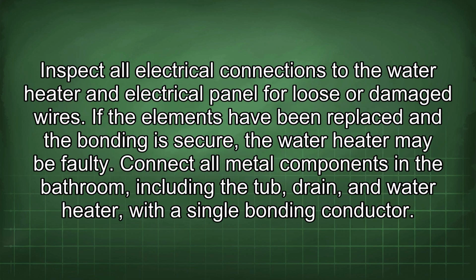Temporarily disconnect the bonding wire between the water heater and tub drain to eliminate the possibility of a ground loop. Inspect all electrical connections to the water heater and electrical panel for loose or damaged wires. If the elements have been replaced and the bonding is secure, the water heater may be faulty. Connect all metal components in the bathroom, including the tub, drain, and water heater, with a single bonding conductor.